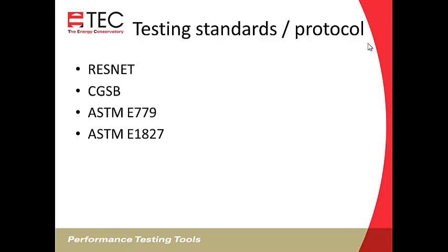ASTM E779 requires data at least 6 data points between 25 and 60 pascals, and needs to be done in both positive and negative. So you need to pressurize and depressurize to follow that standard.